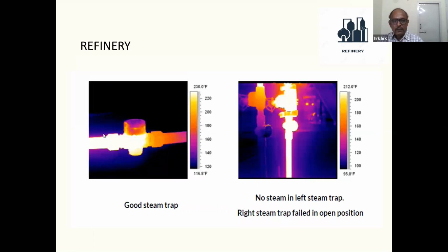Another important item is the steam trap. We will not know that steam is leaking from the trap, and that results in a very huge loss of money, as we can imagine. On the left side is a good steam trap. There is no steam coming from the steam pipe and no hot spot on that side, so it is working all right. Whereas on the right side, it is completely passing the steam. So the steam will be continuously leaking from the system, and we will have a lot of steam loss.